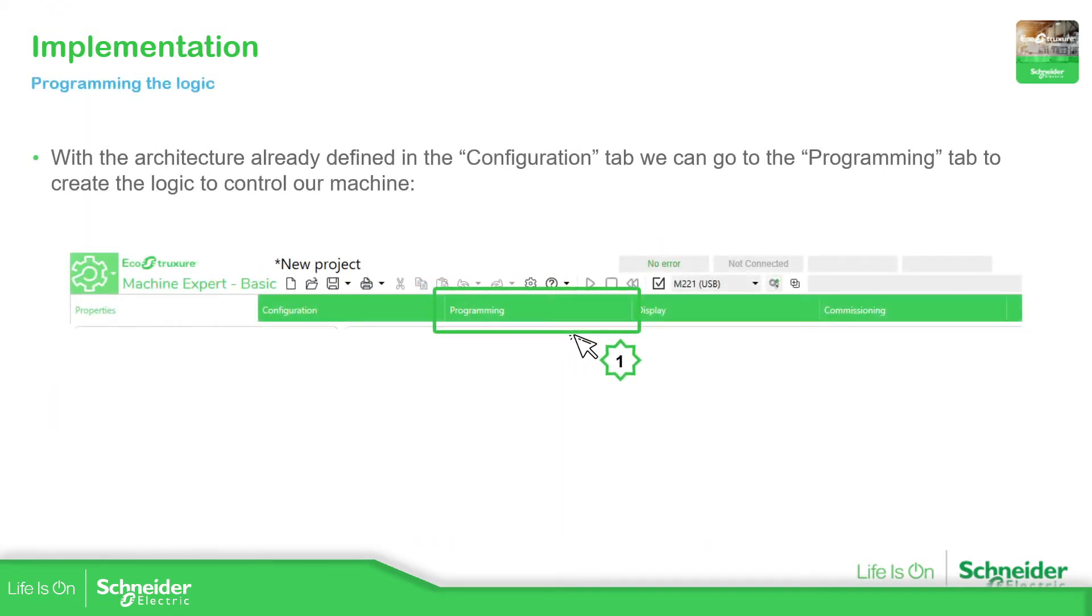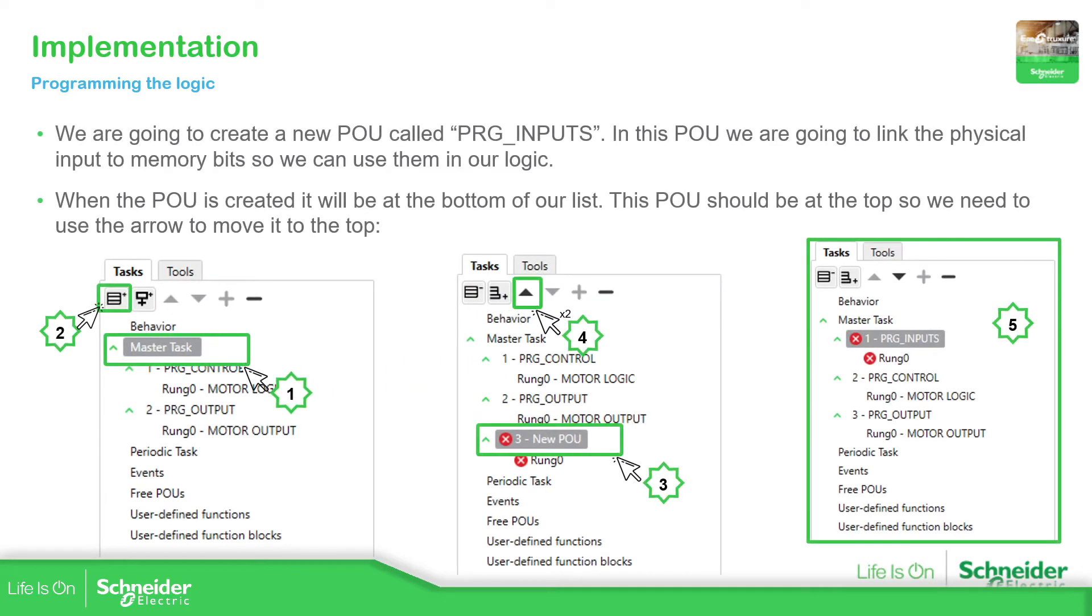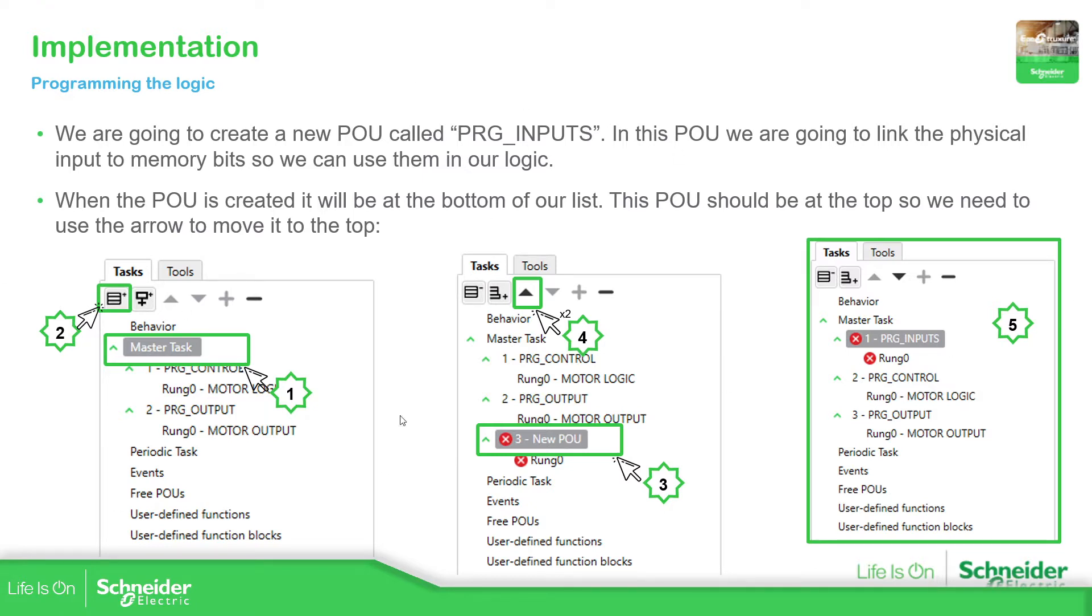What we need to do is go to the programming part and then add a new POU. This POU will be in charge of moving the digital value of the inputs to %m variables, so we can use those %m variables in our code directly. So this is the process what we need to do.